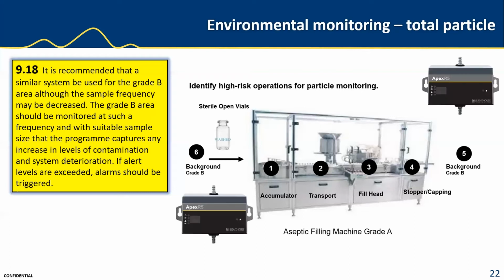And just for your information, when I use the term continuous monitoring, I'm referring to monitoring continuously throughout the aseptic fill process, including the assembly stage. It's not 24/7 monitoring, only during aseptic production. But I would recommend, as I said earlier, 24/7 monitoring of temperature and relative humidity and differential pressure. Again, DP is critical. If differential pressure is lost within the rooms, then contamination risks from lower grade rooms is very probable. But getting to section 9.18, I would actually recommend that you monitor your grade B background areas that are supporting grade A at the same frequency as the grade A.